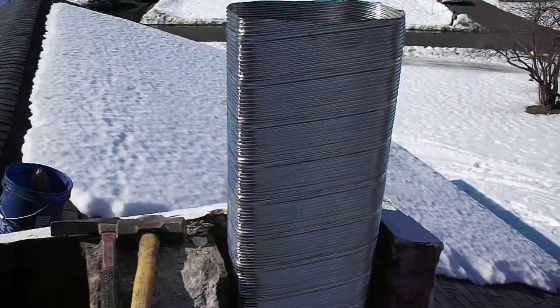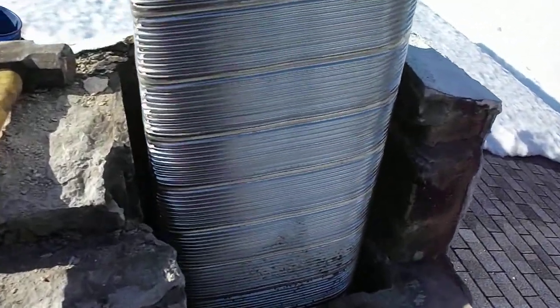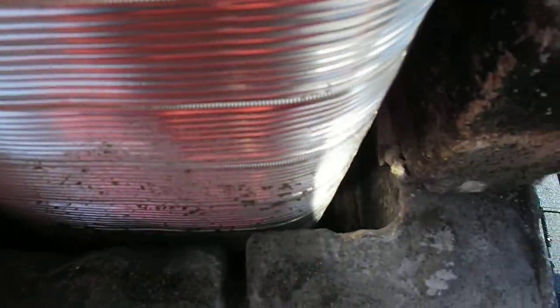This is a stainless steel liner, ten by six and a half, we have in this masonry structure — we just gutted it from the fireplace. The reason we wanted to fit a ten by six and a half is because we need one inch of insulation all the way around it.